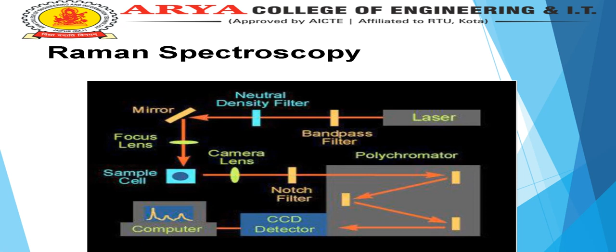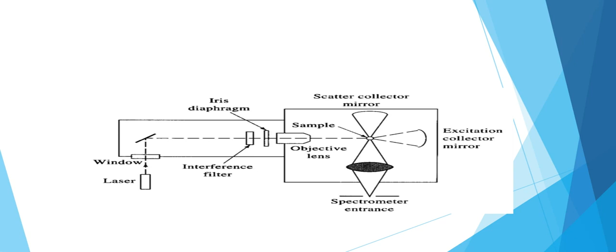A Raman spectrometer typically consists of 4 major components. First is the excitation source, a laser; second is the sample illumination system and collection optics; third is a wavelength selector; and fourth is a detector. This is the block diagram of the Raman spectrometer. Again, this is the internal diagram of a Raman spectrometer: laser, window, interference filters, iris diaphragm, scatter collector, sampling, objective lens, spectrometer entrance, excitation collector, mirror.